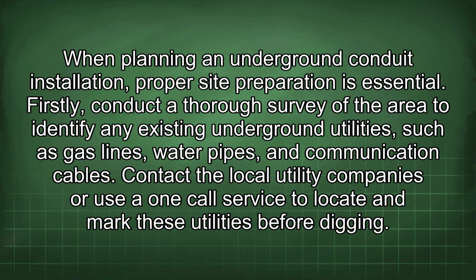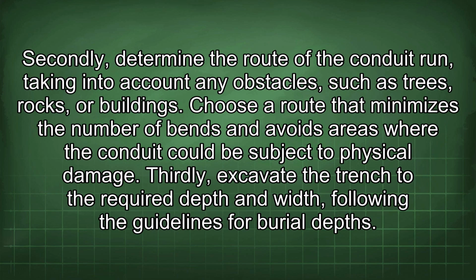When planning an underground conduit installation, proper site preparation is essential. Firstly, conduct a thorough survey of the area to identify any existing underground utilities, such as gas lines, water pipes, and communication cables. Contact the local utility companies or use a one-call service to locate and mark these utilities before digging. Secondly, determine the route of the conduit run, taking into account any obstacles, such as trees, rocks, or buildings. Choose a route that minimizes the number of bends and avoids areas where the conduit could be subject to physical damage. Thirdly, excavate the trench to the required depth and width, following the guidelines for burial depths.